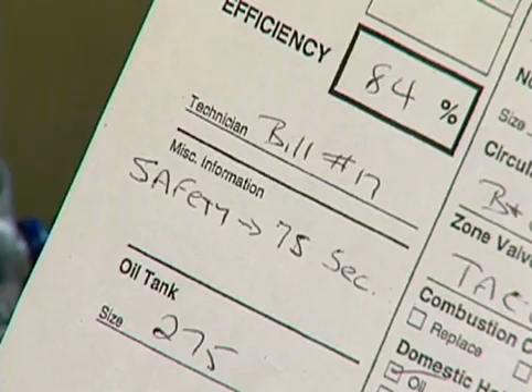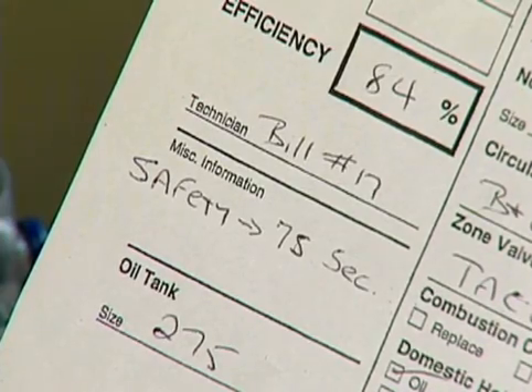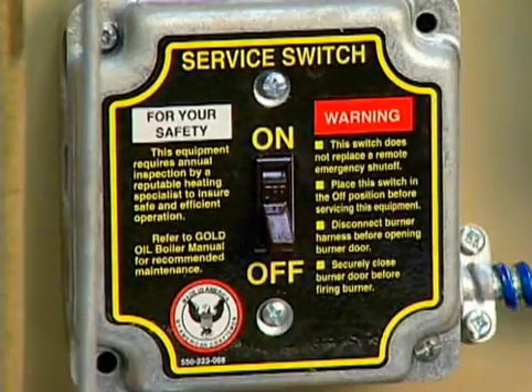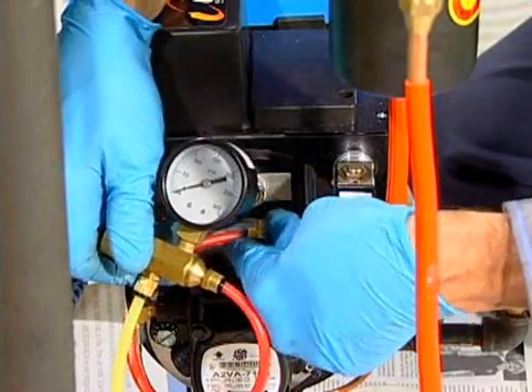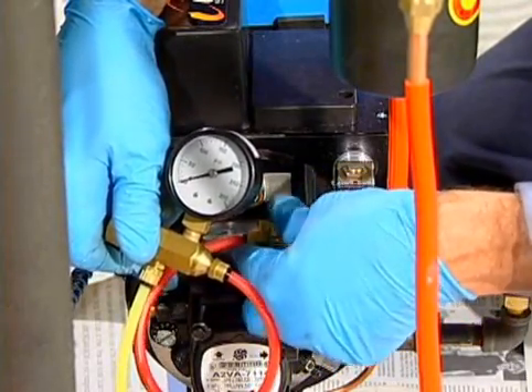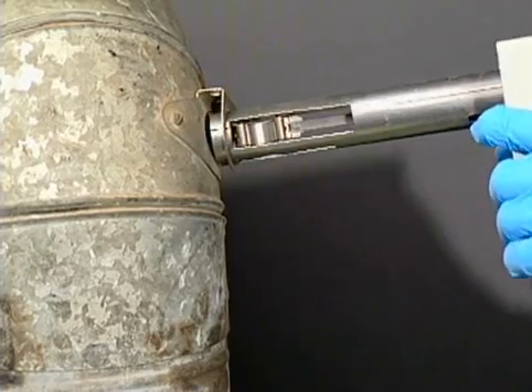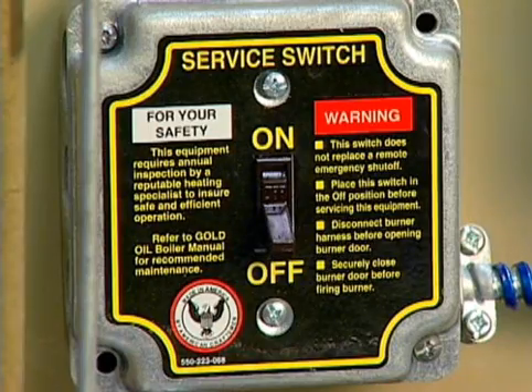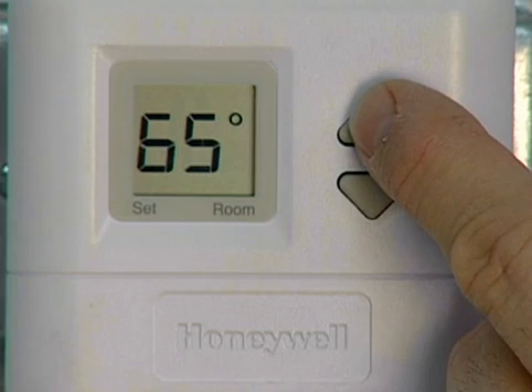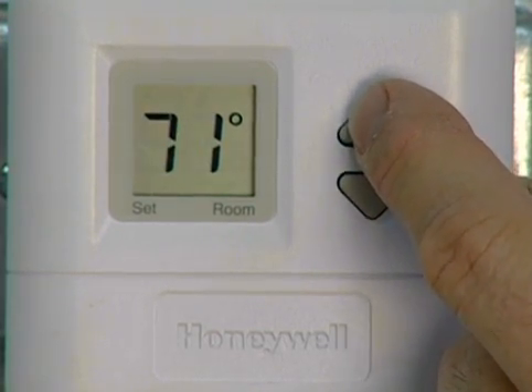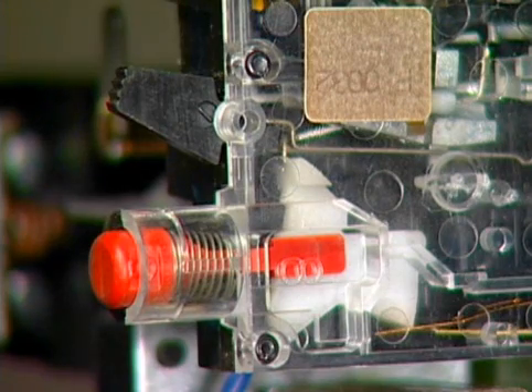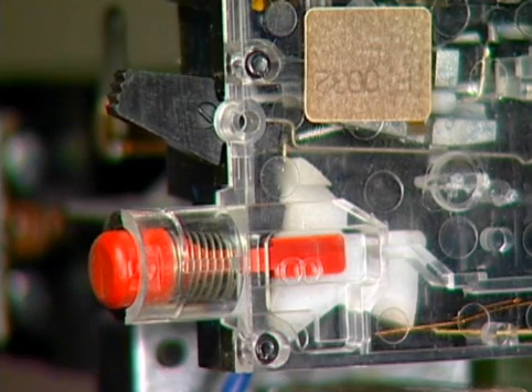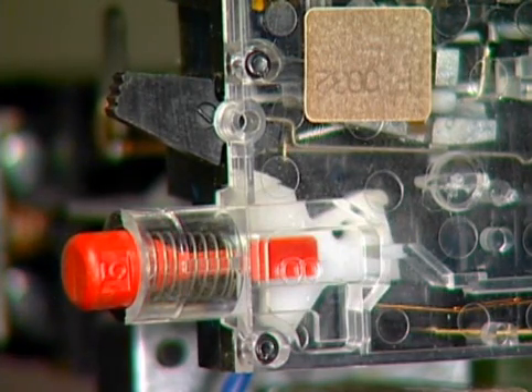It's important to check the safety timing of primary controls every time you perform a service call. Note the timing on your service invoice. To check the safety timing, turn off the electrical supply. Either block the flow of oil by installing your pressure gauge in the nozzle port, or remove the stack switch from the flue pipe. Turn on the electrical supply. Make sure that both the line and low voltage circuits are complete. The control should energize and shut off on safety in approximately 75 seconds.